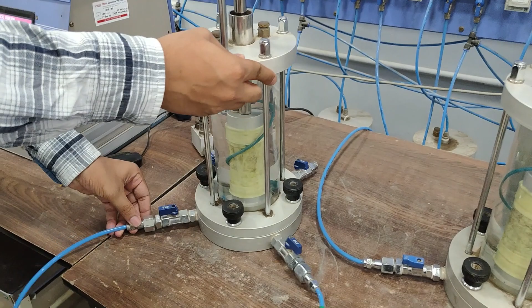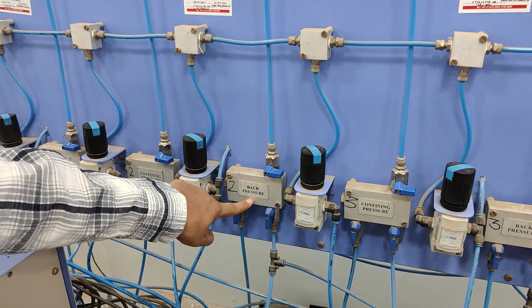So this knob you can see here is the cell pressure knob, which has been connected through an outer hole, and this pressure will be applied through these valves. As you can see, these are the confining pressure and back pressure valves. Pressure will be regulated through this pressure regulator. So we will apply some confining pressure.